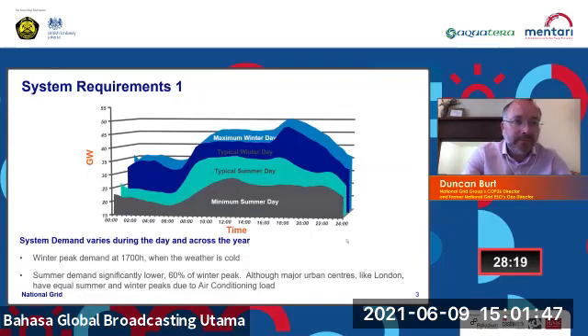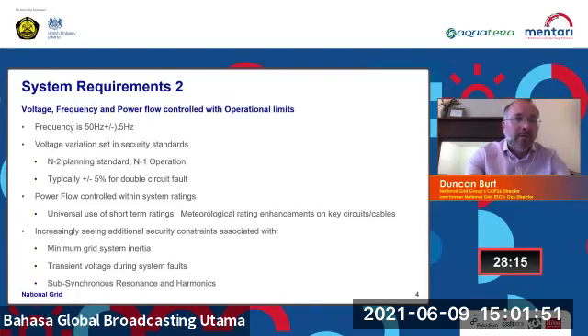That summer versus winter peak differential drives a number of design criteria for the system. For example, most outages on the grid are taken during summer months when demand is lower, same for generation and supply arrangements. The UK grid operates at 50 hertz frequency, plus or minus 1%. For network reliability, the system is planned to N-2, remaining secure through a planned maintenance outage plus a fault outage loss, i.e. two events. During operational timescales, it's continually planned to N-1, so demand remains secure for the first fault.